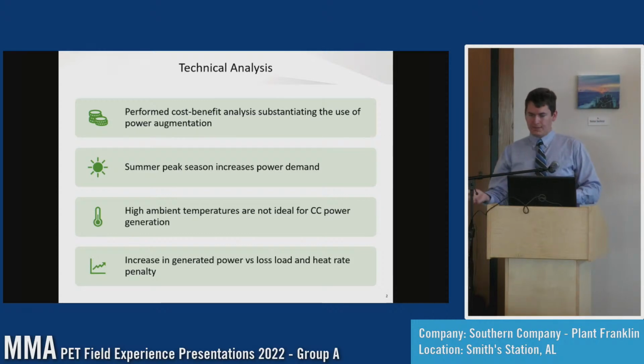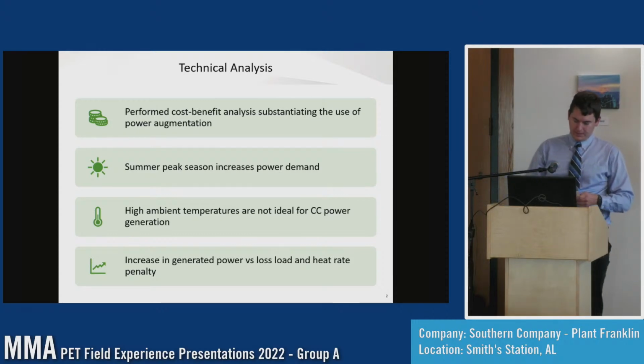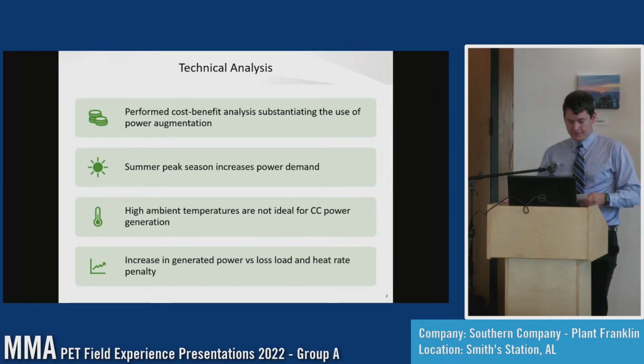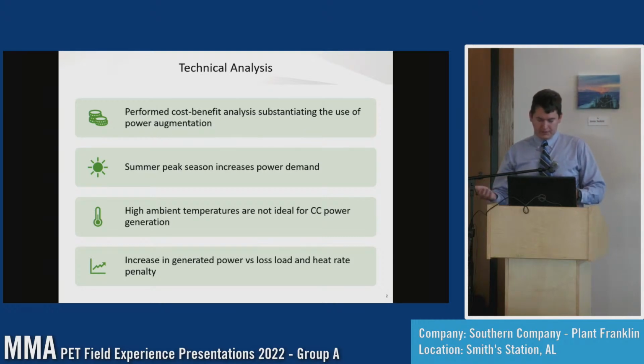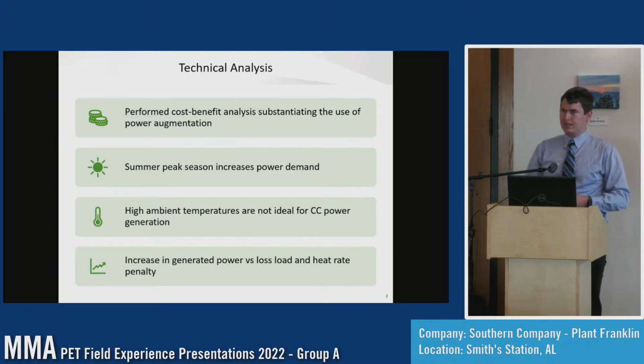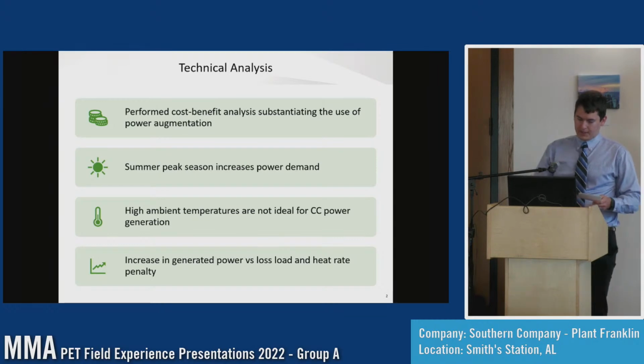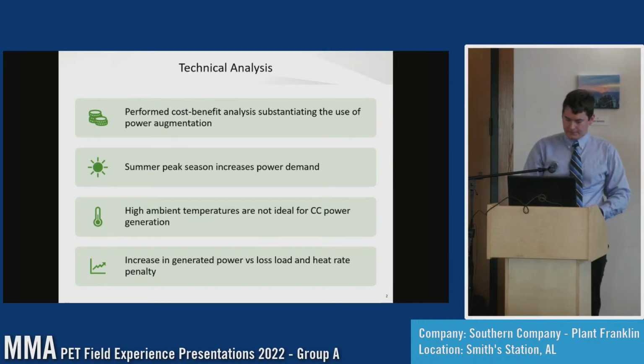However, since it's robbing steam from the steam turbine that could have been reused in the steam cycle, there's a loss in efficiency and therefore a cost. That cost is a lost load and an increase in the heat rate. My objective was to find if Power Aug revenue outweighed those costs, the lost load, and the increased heat rate.